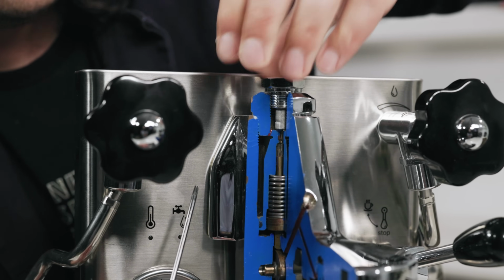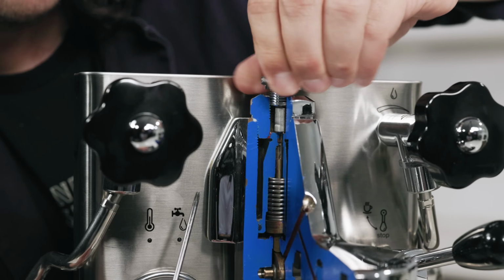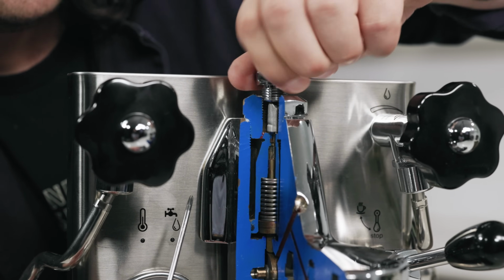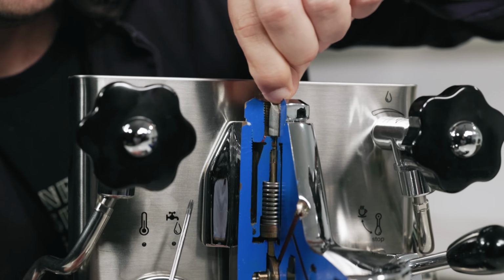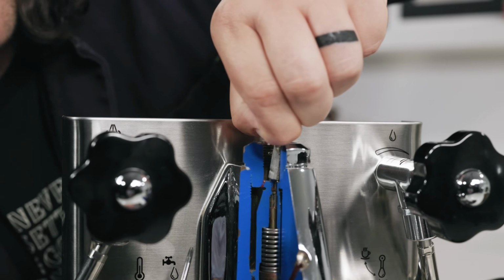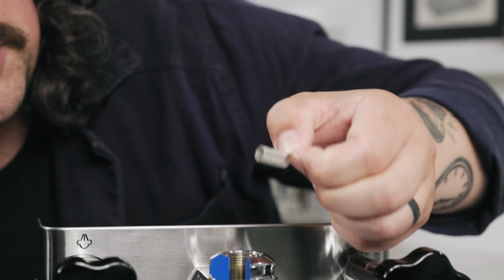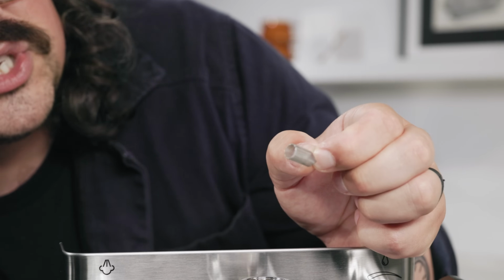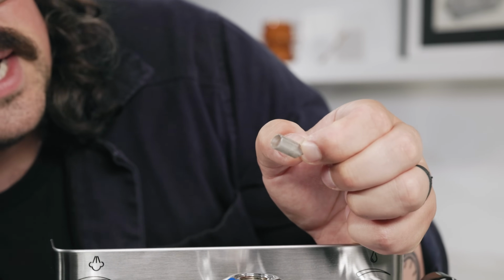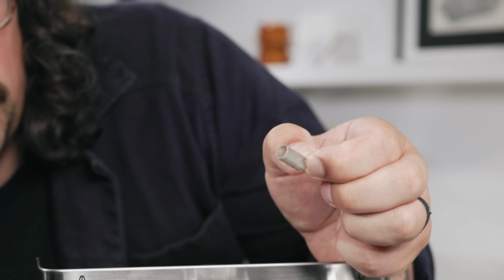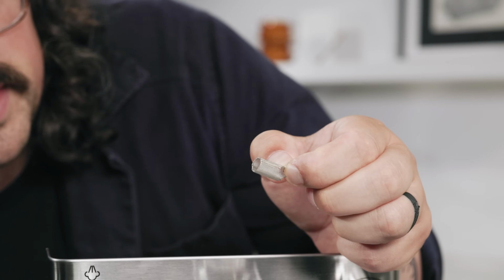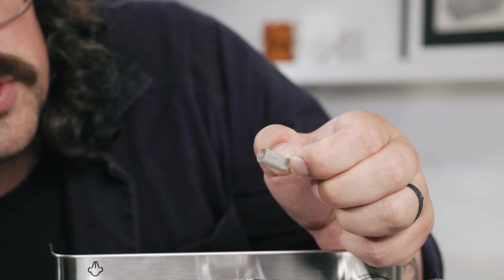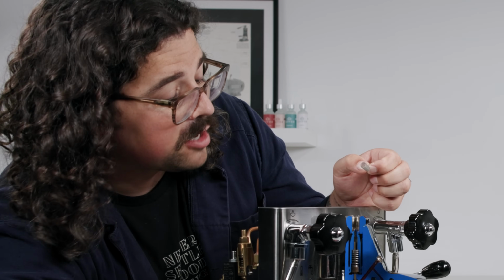And what you see is underneath this mushroom cap, there's a little filter that is built into a lot of these machines, like so, to stop coffee particles or anything like that from getting into the Jiggler, because that Jiggler's orifice is so small that any slight thing can clog it. So if you're having issues where water's not entering your group head, it could be because the Jiggler is scaled over or there's particles that are blocking it.